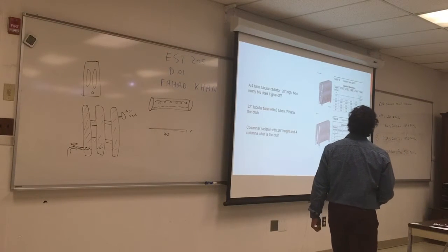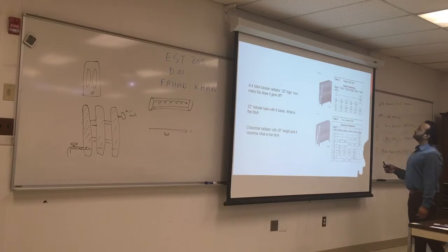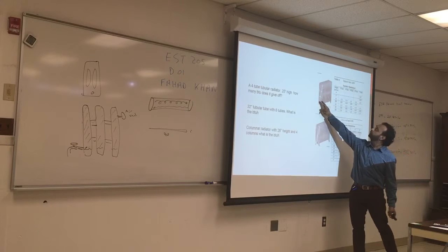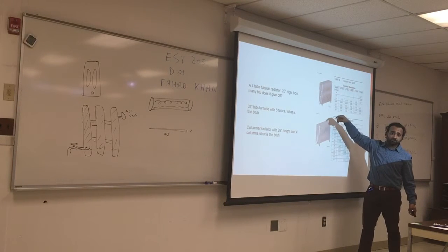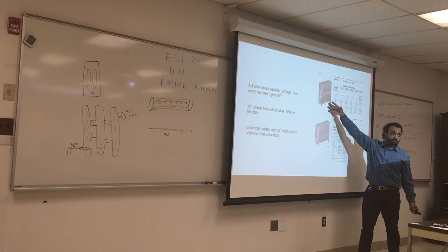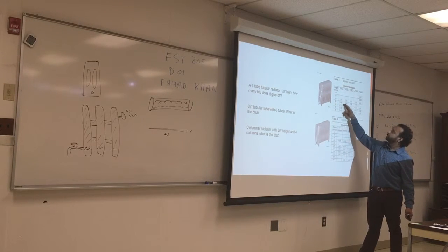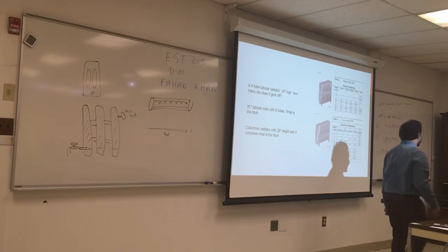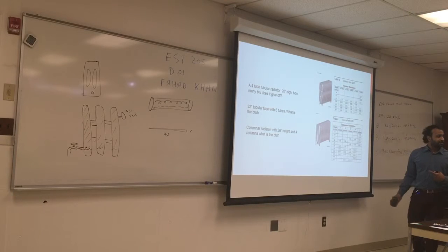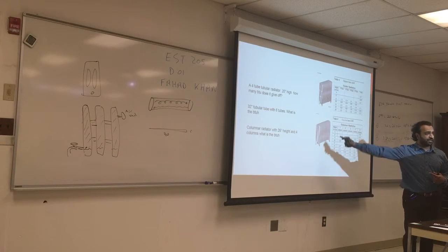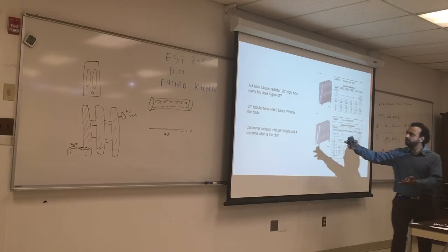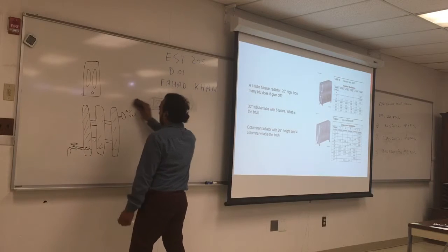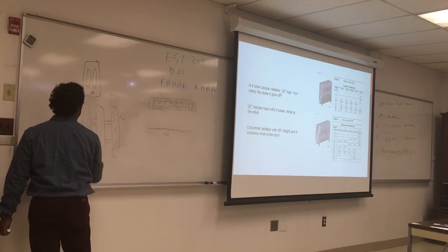A few more. This is another convector. It's called tubular radiation. And again, see there are many selections. You can have 2 tubes. You have it high or low, so you can order whatever size you want based on your space. So again, it's a lookup for the EDR, the same conversion. Let's do these. Does it make sense to you? Is it clear? So you just pick up the number of EDR, you multiply by 240, and the 240 is fixed. 240, yeah.